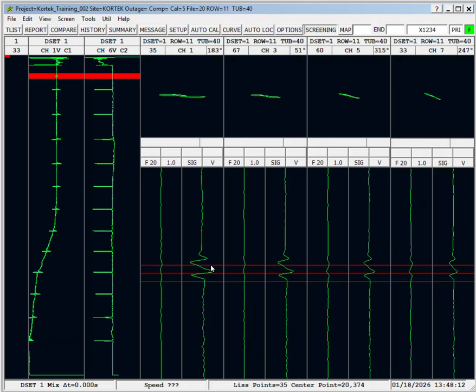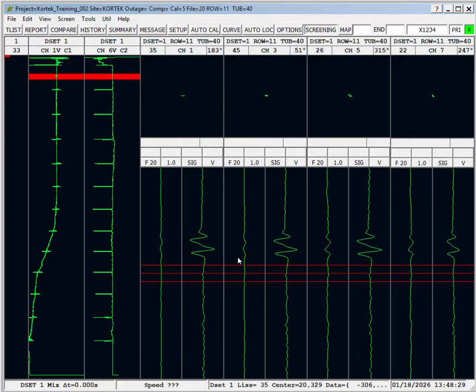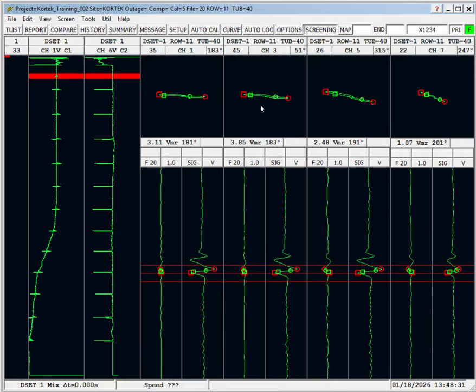So you have to take cal standard signals sort of with a grain of salt. They're not going to look exactly the same when you encounter, like in this case, a dent in an actual heat exchanger tube. But typically the rotation doesn't change much when you go up or down in test frequencies. Now we'll look at some other ones that are going to remain extremely flat, but in this case, there's a little bit of rotation in there.